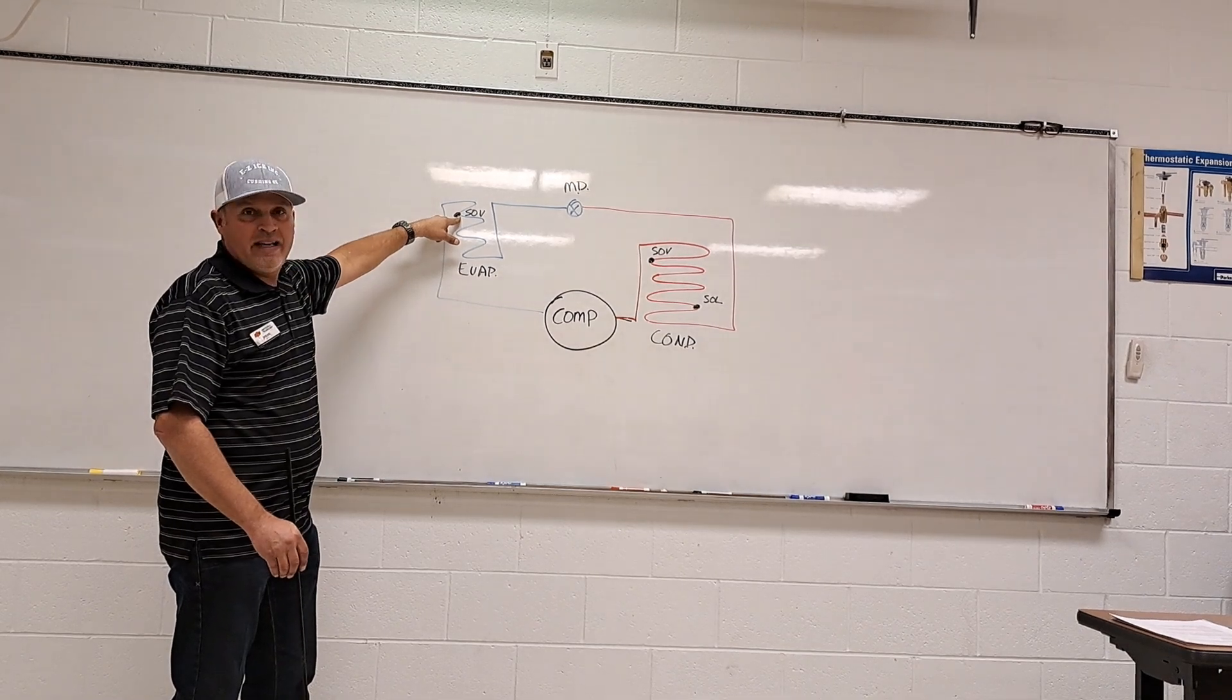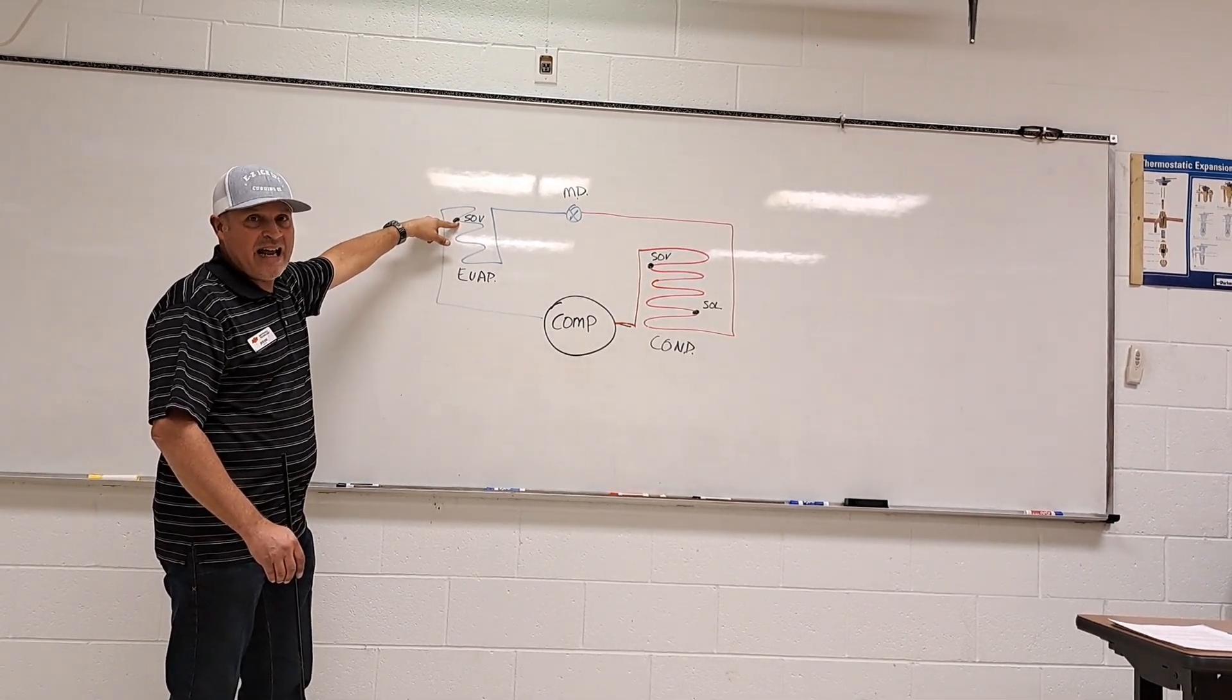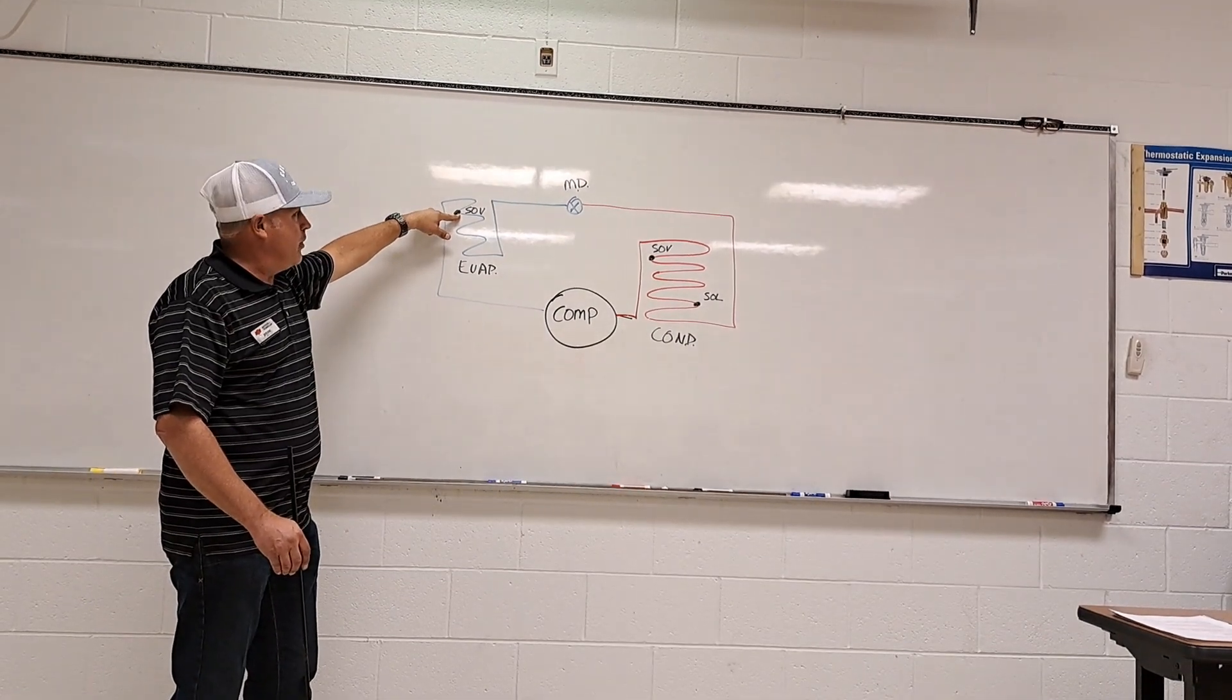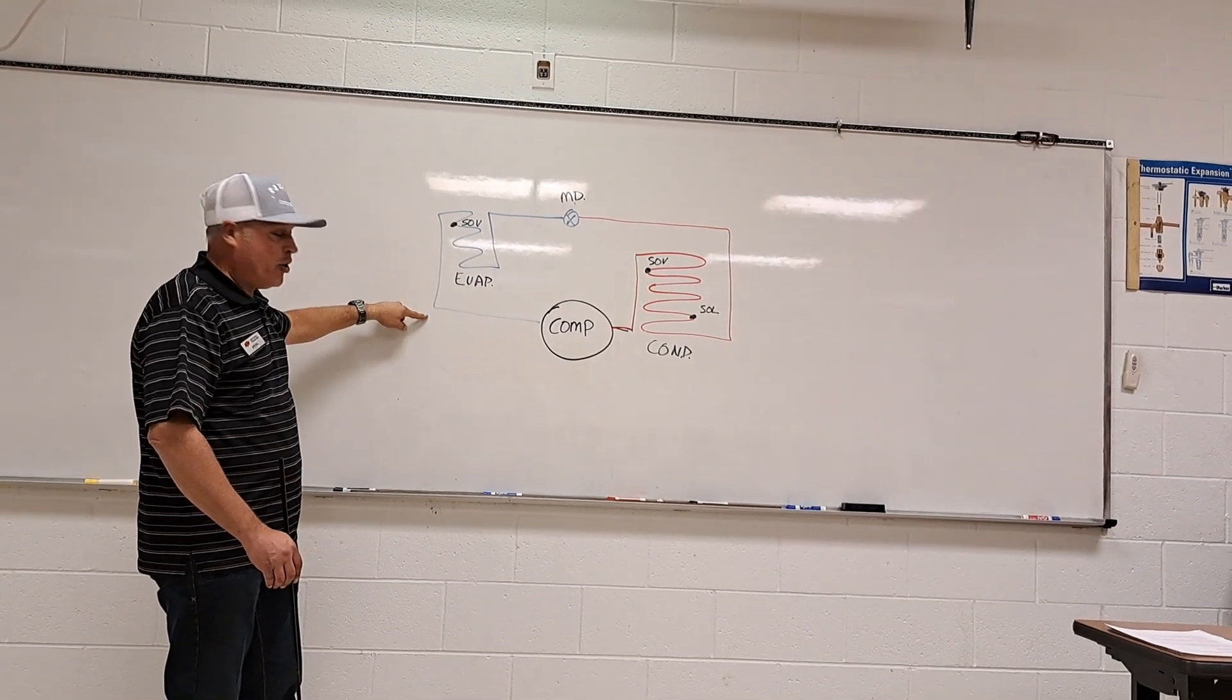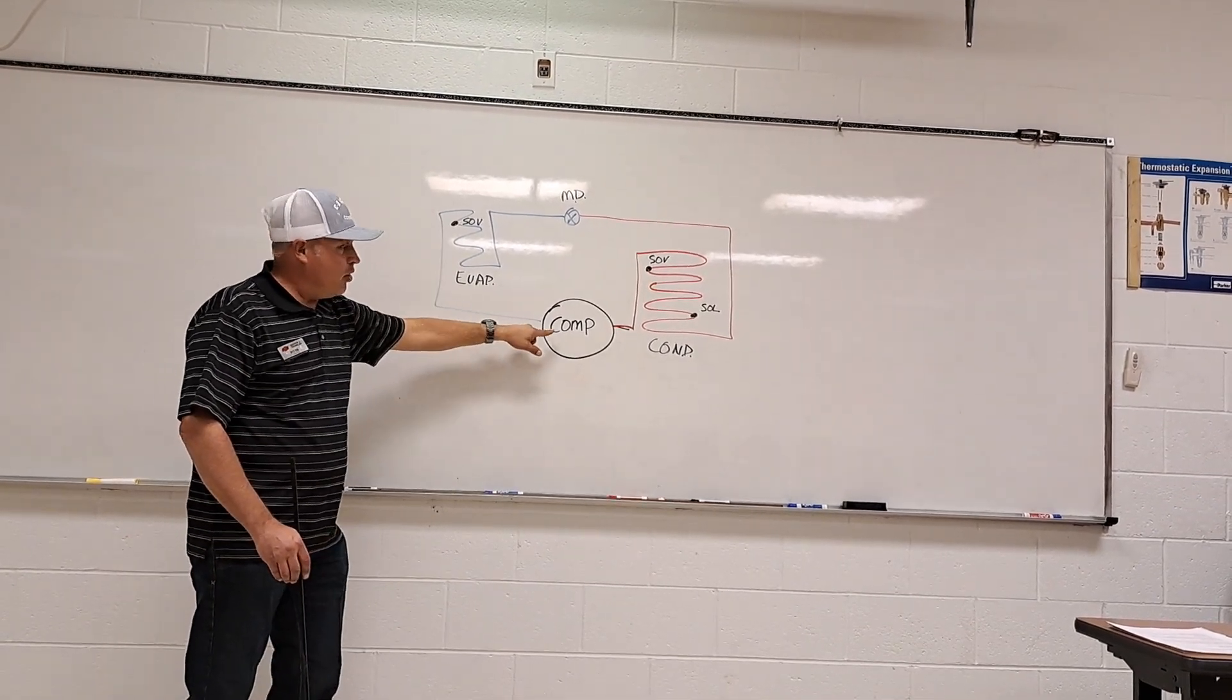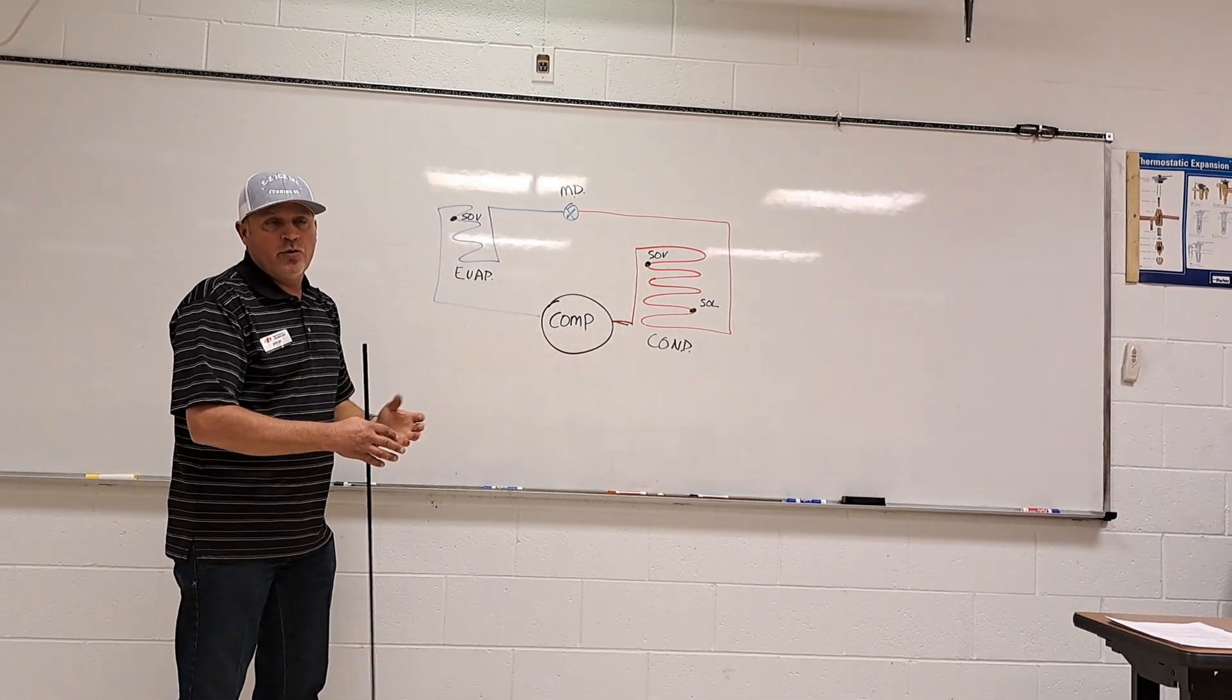This is where we begin to superheat. Superheating is any heat added to a vapor above its saturation point. We continue superheating through our suction line all the way back into our compressor, and this is where most superheat occurs.